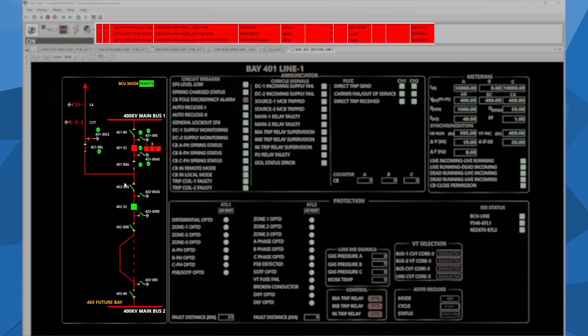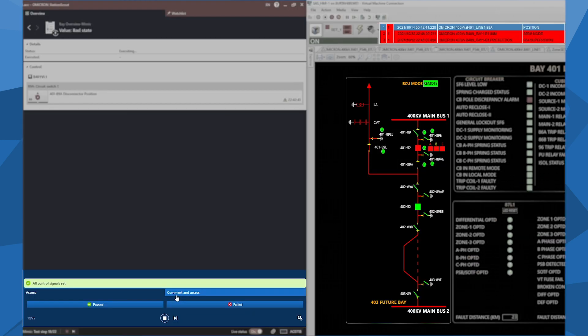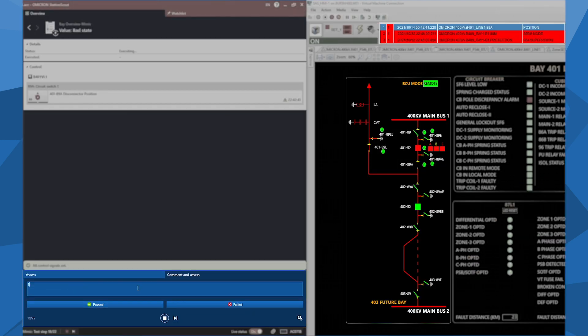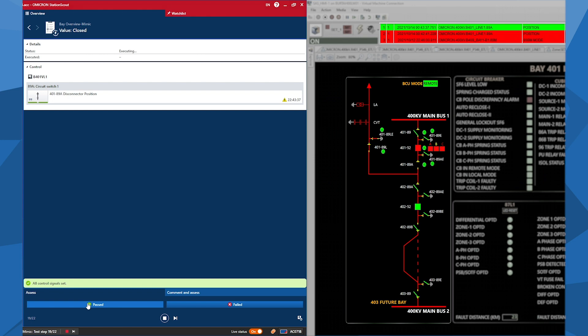And when you have a bad state position in this reaction matrix of the HMI, I map this to receive an alarm for that, and I received this alarm. That means I can have also multiple destinations like the first destination to check would be the mimic diagram, the second one would be alarm. And you can also have some more to check the event log if you want to check. You can check all, and you can enter a command with that. So I can enter a command like single line diagram checked, or you can say okay and the bay overview is okay, the alarm okay. So with that, you can have these commands in your test report. So now I say passed, and it's back again to its closed position, so it's okay for me.